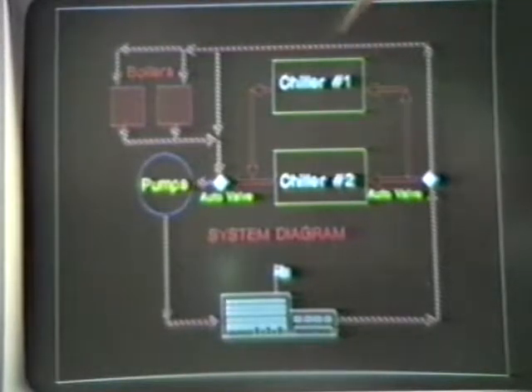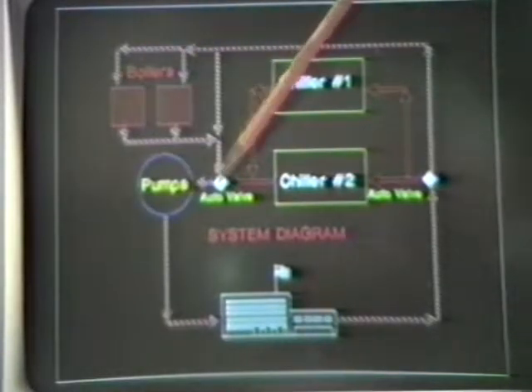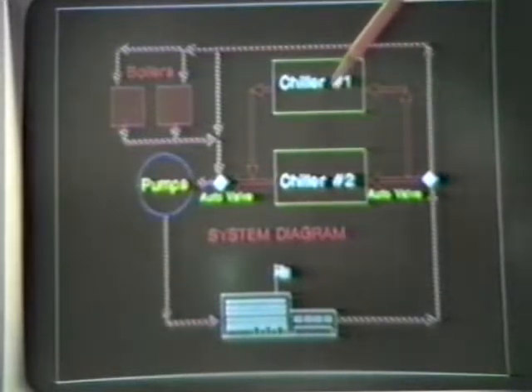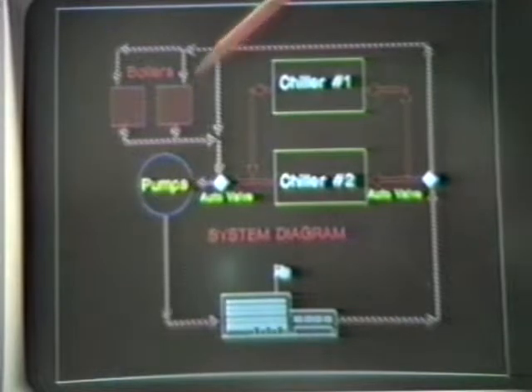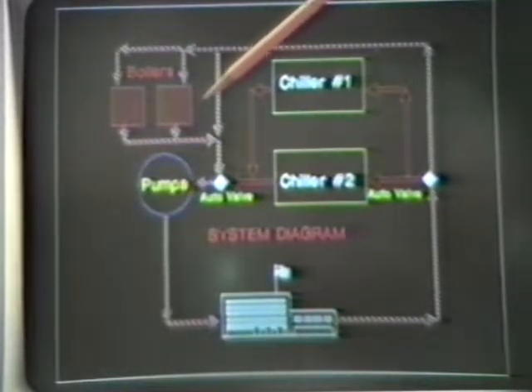Now we can see on our diagram that our system has now changed over into the heating mode. The control valves have stopped flow through the chillers, and we're now going through the boilers. There is another control on our hot water heating system that bypasses the boiler for minimum or mild weather operations. When full hot water is not needed, we bypass all or part of the water to get an efficient firing operation from the boiler.